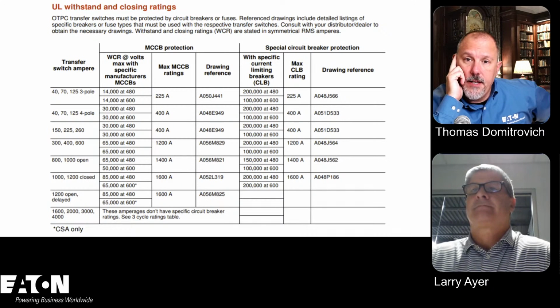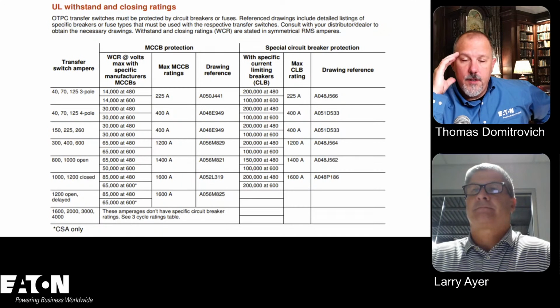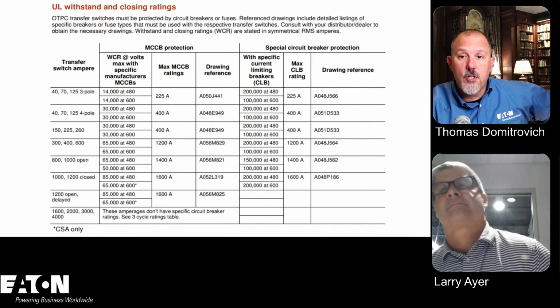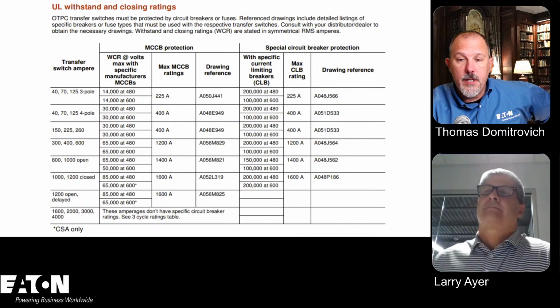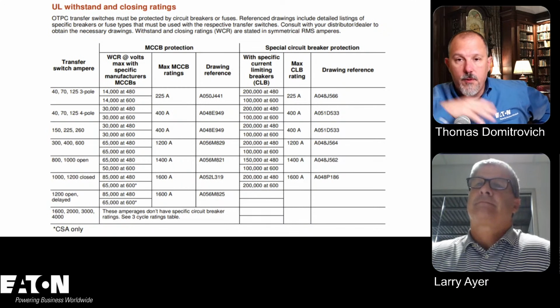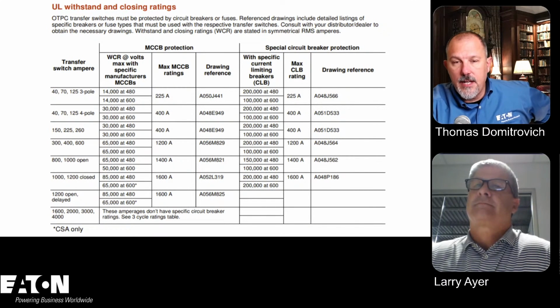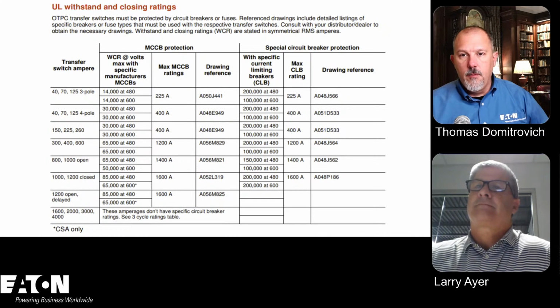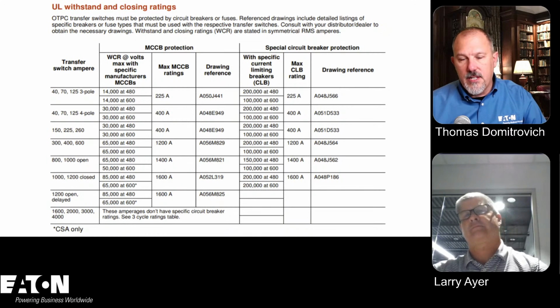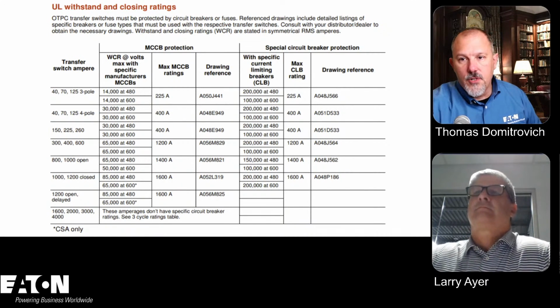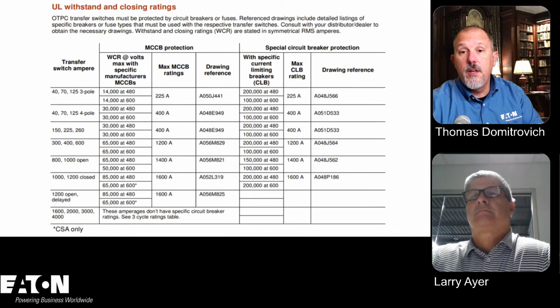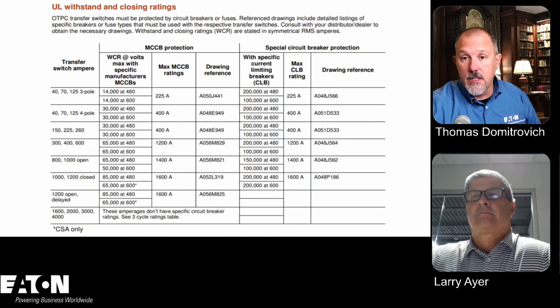Now the withstand close-on rating. We use the terminology withstand close-on ratings with transfer switches, but it's very similar to a short circuit current rating for that equipment. We don't use the term short circuit current rating, we use withstand close-on ratings, but they're used synonymously with regard to the code when it says that you have to have an SCCR rating equal to or above the available fault current, like in Articles 700, 701, 708, etc. But we label it with a withstand close-on rating, and these transfer switches ship with specifics that tell you what withstand close-on rating they will achieve based upon the overcurrent protective devices upstream.